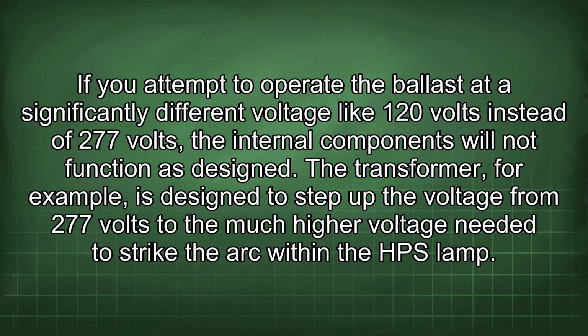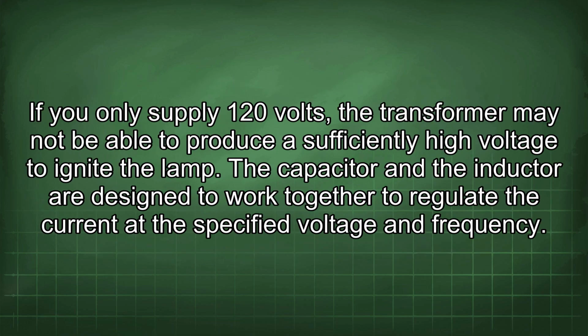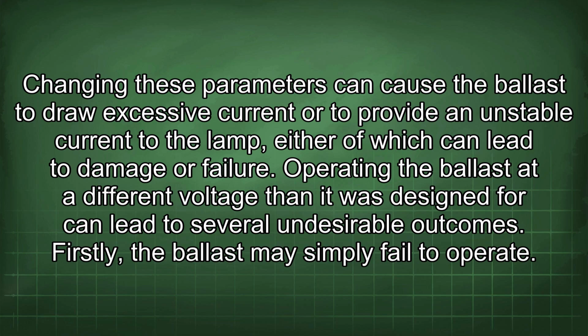If you attempt to operate the ballast at a significantly different voltage like 120 volts instead of 277 volts, the internal components will not function as designed. The transformer, for example, is designed to step up the voltage from 277 volts to the much higher voltage needed to strike the arc within the HPS lamp. If you only supply 120 volts, the transformer may not be able to produce a sufficiently high voltage to ignite the lamp. The capacitor and the inductor are designed to work together to regulate the current at the specified voltage and frequency. Changing these parameters can cause the ballast to draw excessive current or to provide an unstable current to the lamp, either of which can lead to damage or failure.